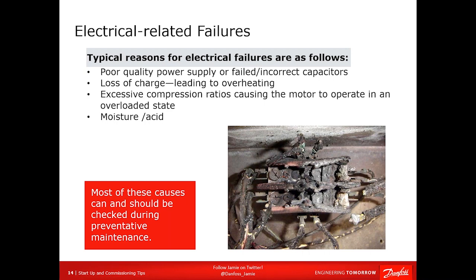Loss of charge. Again, slow loss of charge is a lot harder to catch than a quick loss of charge. If something's hissing out the side of the evaporator, that's easy to catch. But how do you catch losing 20% of your charge every year? All right, that's a tougher one to get. However, it's easy to catch with nitrogen pressure testing and a micron gauge.